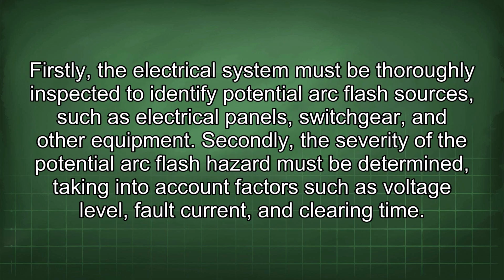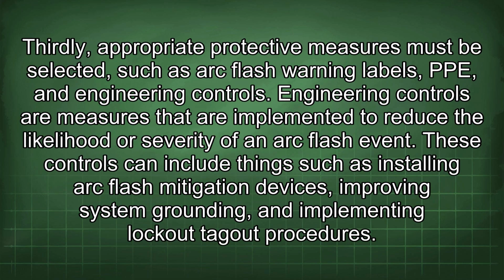Firstly, the electrical system must be thoroughly inspected to identify potential arc flash sources, such as electrical panels, switchgear, and other equipment. Secondly, the severity of the potential arc flash hazard must be determined, taking into account factors such as voltage level, fault current, and clearing time. Thirdly, appropriate protective measures must be selected, such as arc flash warning labels, PPE, and engineering controls.